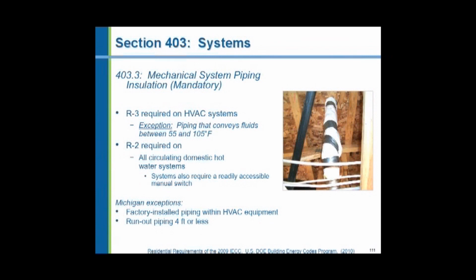The exception is domestic hot water systems. They're not required to have any insulation on the hot water that you supply to the faucets in your bathrooms, with the exception if you have a recirculating hot water system. Then the entire supply and return system must be insulated to the value of R2, or 2/3 of an inch of fiberglass.